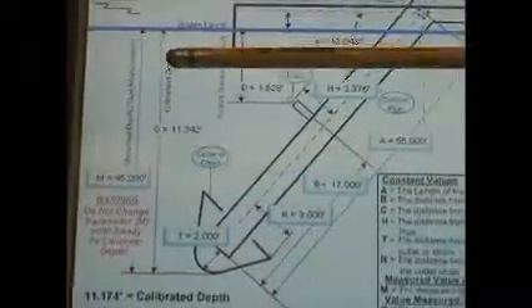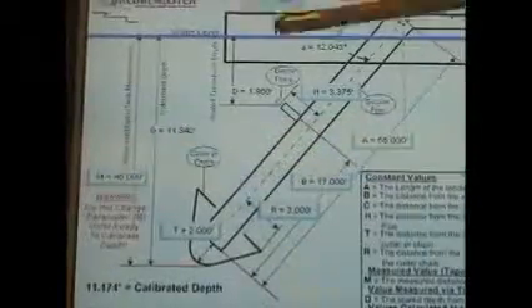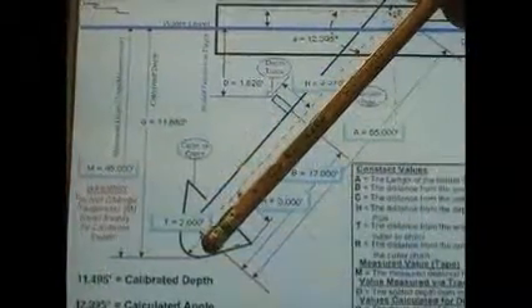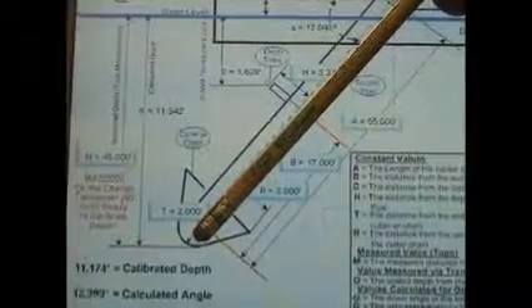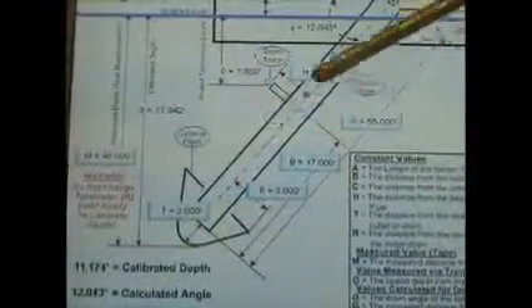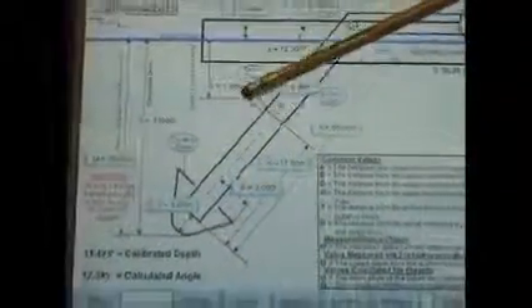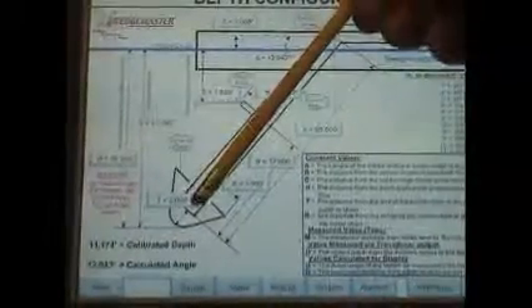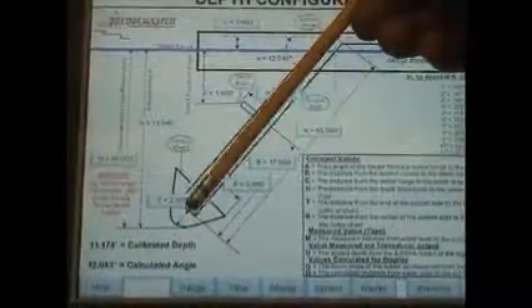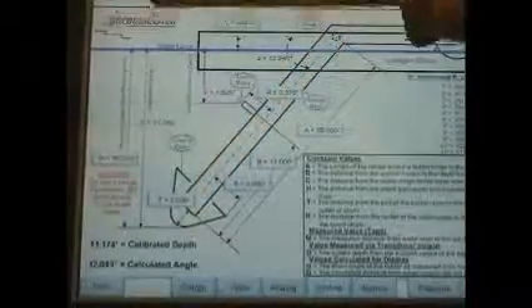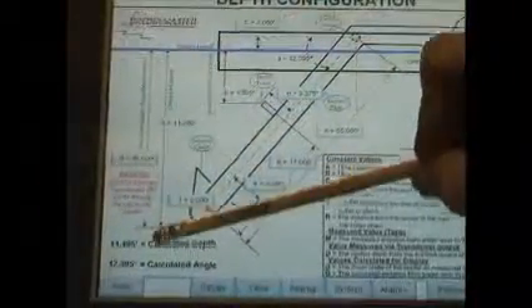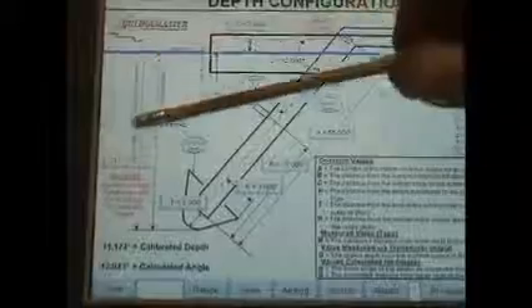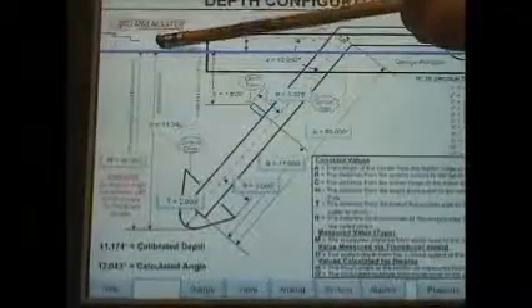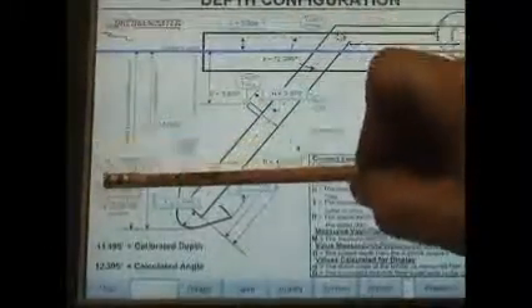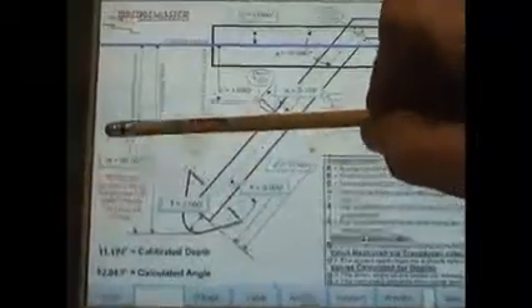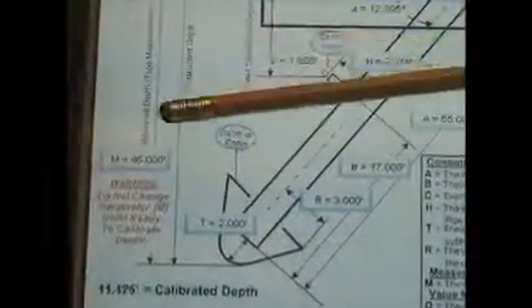So to get the calibration correct, leave the ladder down in the water at whatever depth you want, as long as the transducer is under the water a ways. The deeper the better that you're going to be digging at. Lower it to that depth and then measure what the actual tape measure says. What the tape measure gives you, you need to enter in as M. That will be the tape measure reading right here.